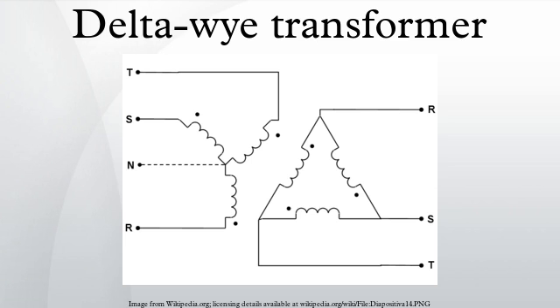Delta-Y transformers introduce a 30, 150, 270, or 330 degree phase shift. Thus they cannot be paralleled with Y-Y transformers. However, they can be paralleled with identical configurations and some different configurations of other delta-Y transformers.